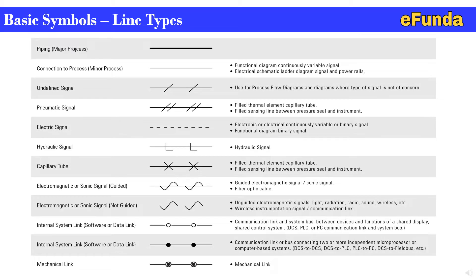In this slide we see basic symbols and line types. A complete table defines various kinds of lines. The major process piping is shown by a dark thick line; connection to process is a minor dark line with a thin line. Functional diagram continuously variable signals, electric schematic, ladder diagram signal, and power rail use an undefined signal line — a single line through two cross lines — used for process flow diagrams where the type of signal is not of concern. Pneumatic signal is a dark line with two cross lines. Filled thermal element capillary tube or filled sensing line between pressure seal and instrument is also shown.